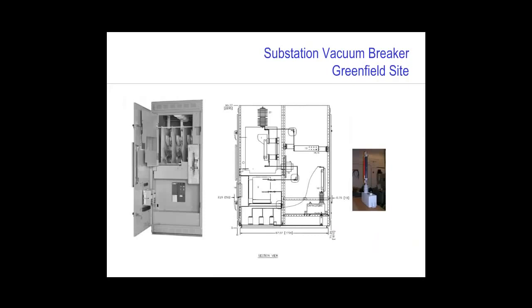Here we're showing you essentially the same MSB medium voltage load break switch over fixed mount vacuum breaker assembly, but this one was applied in a greenfield site. Actually, in this site there were 12 unit substations. Some were low and some were medium voltage secondaries, but each applied an MSB assembly on the primary. In this case you can see in the upper front compartment also a lightning arrestor, and also in the lower rear compartment the snubber network, which is integral and part of the assembly shipped from the factory.